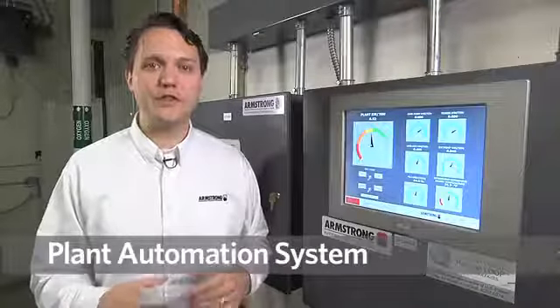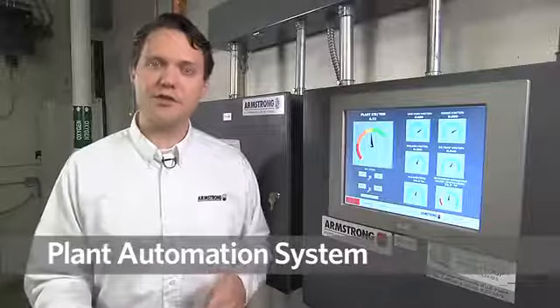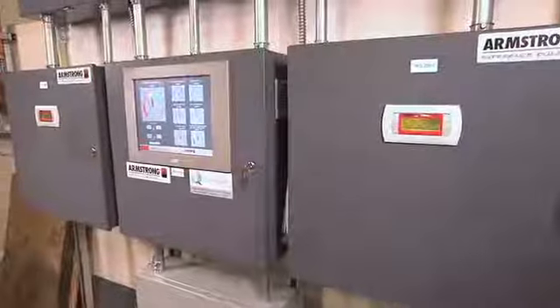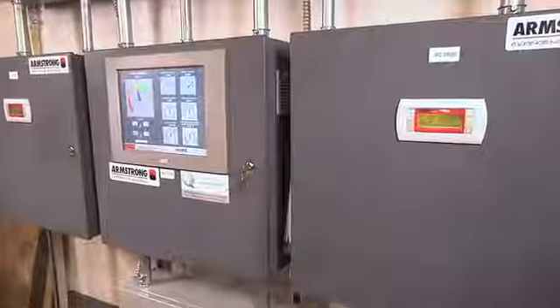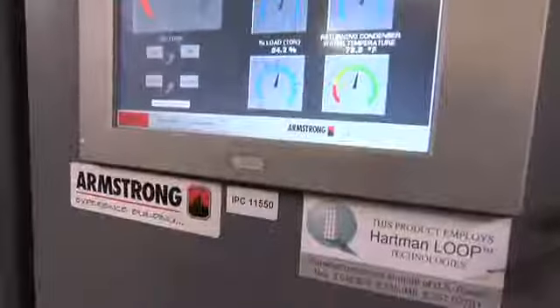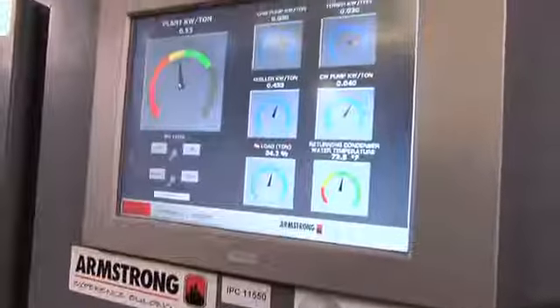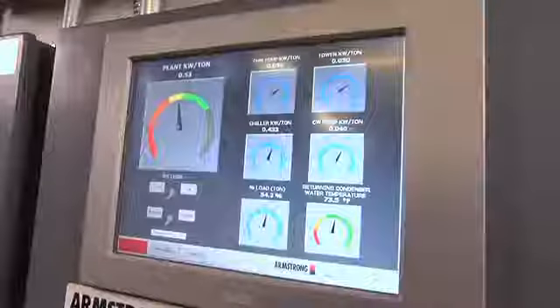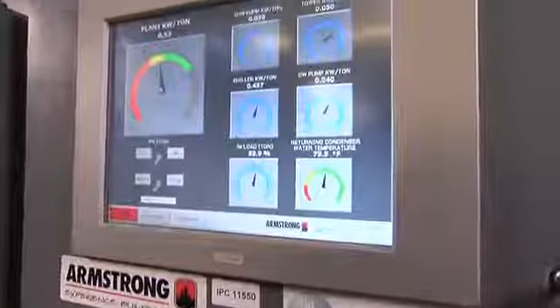Here we are at the chiller plant optimization system where the Armstrong controls have been installed. It's our model IPC 11550, and it controls the entire plant. It replaced a previous control system that was mainly used for data logging. The previous system was a constant chilled water primary, variable secondary, that was replaced with an all variable primary chilled water plant. On the condenser water side, it was originally constant flow, which was modified to be an all variable condenser water plant.